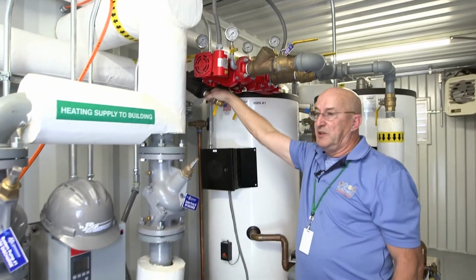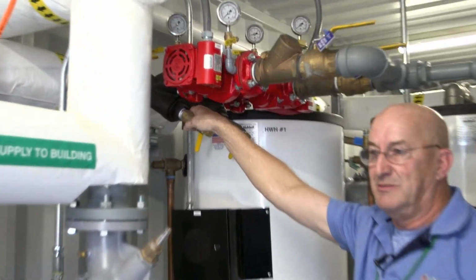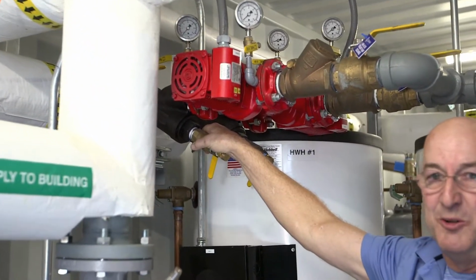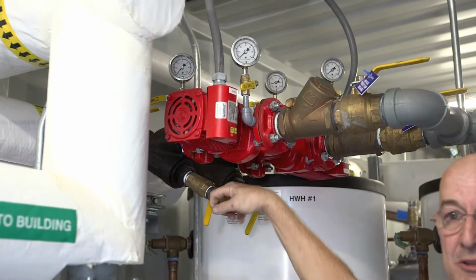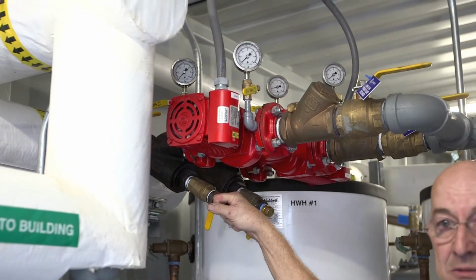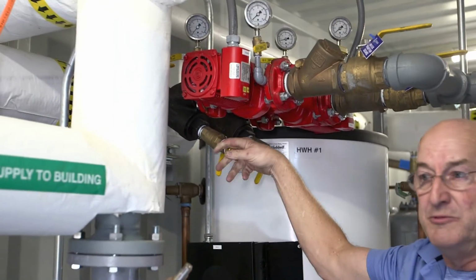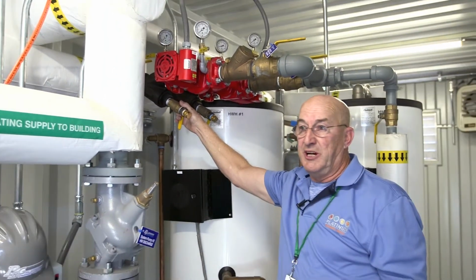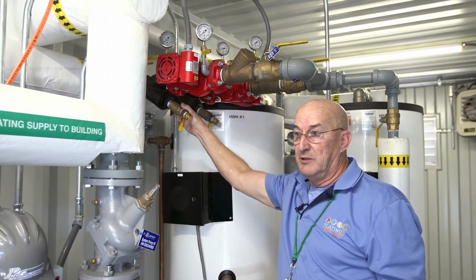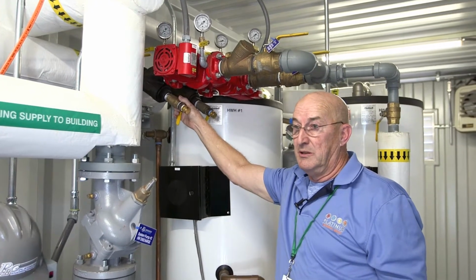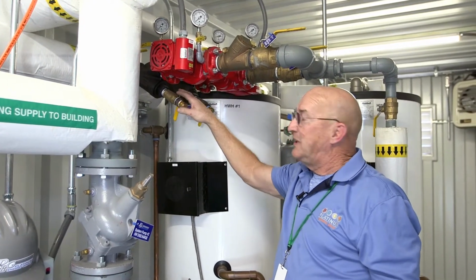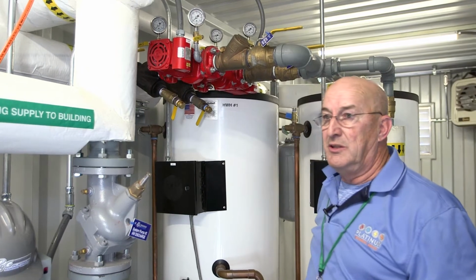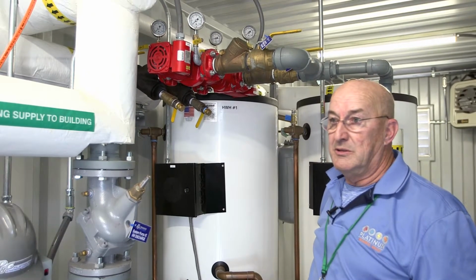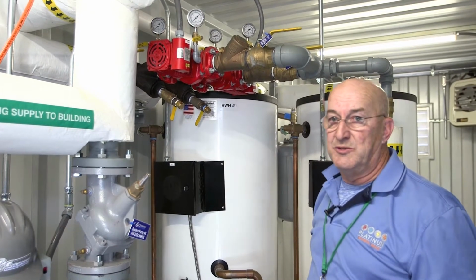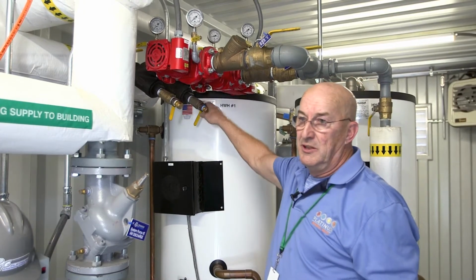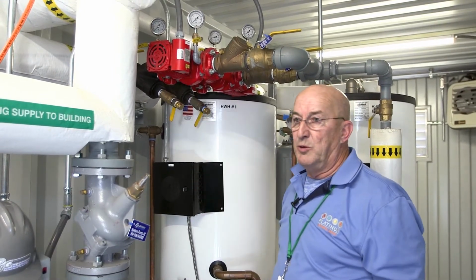You see this Y strainer here. You say, what is this Y strainer for? For people that don't know what it's for. You hook a hose up to this, run it out onto the roof. This should be flushed out at least once a month to make sure there's no sediment buildup in there. That keeps any sediment from getting in the heat exchanger and clogging up the heat exchanger. You don't want to lose a heat exchanger because of dirt. This is to protect it. You keep them flushed, you'll have no problem.